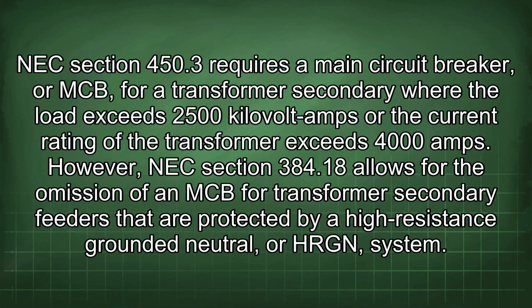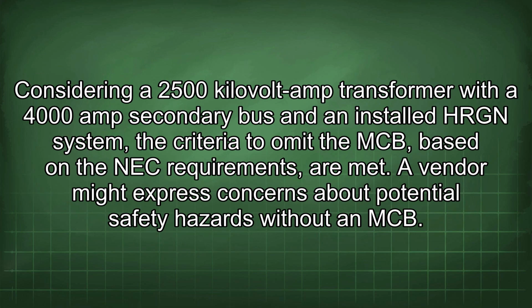NEC Section 450.3 requires a main circuit breaker, or MCB, for a transformer secondary where the load exceeds 2500 kVA or the current rating of the transformer exceeds 4000 amps. However, NEC Section 384.18 allows for the omission of an MCB for transformer secondary feeders that are protected by a high resistance grounded neutral, or HRGN, system. Considering a 2500 kVA transformer with a 4000 amp secondary bus and an installed HRGN system, the criteria to omit the MCB based on the NEC requirements are met.